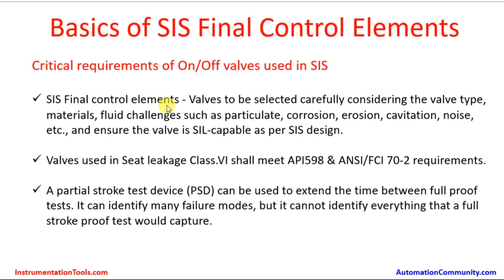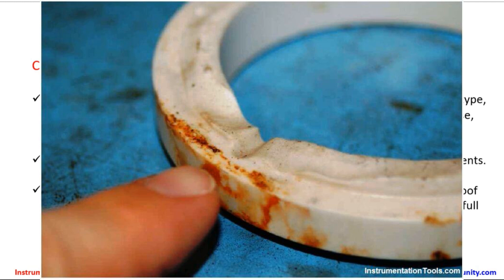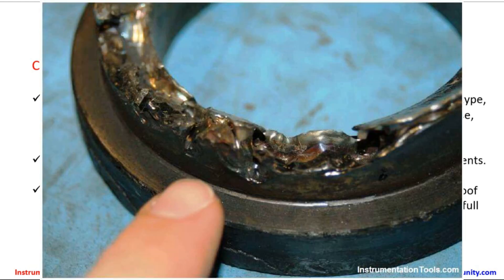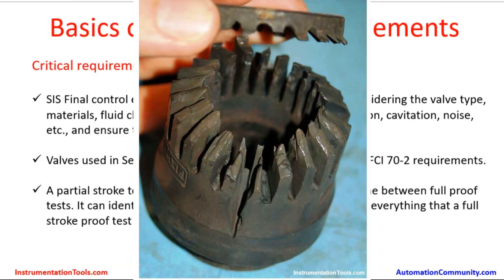Critical requirements for on-off valves used in the safety instrumented system: valves must be selected carefully, considering valve type, materials, and fluid challenges such as particulate, corrosion, erosion, cavitation, and noise. Ensure the valve is SIL-capable as per the SIS design. The chemical process characteristics — such as erosion — can impinge on the valve body, and there is a possibility of erosion or cavitation impacting the performance of the SIS valves.